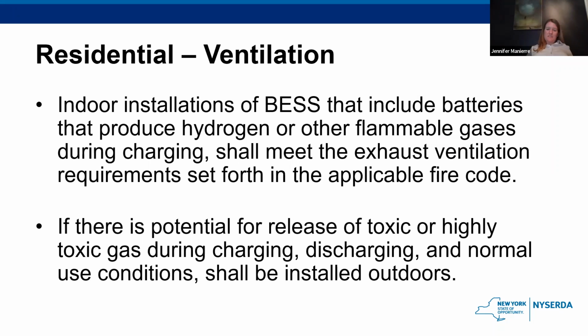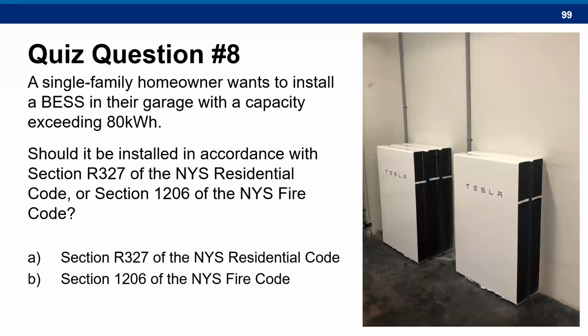Indoor installations that include batteries that produce hydrogen, like we were talking about for lead acid earlier, or batteries that produce other flammable gases during charging, they need exhaust ventilation, much like we had been discussing for the commercial system too. If they're going to be off gassing as part of their normal operation, they need exhaust ventilation. Again, lithium ion is not going to be doing that. And if there is potential for the release of toxic gases during their normal operation, those are always going to be installed outdoors, no matter what.